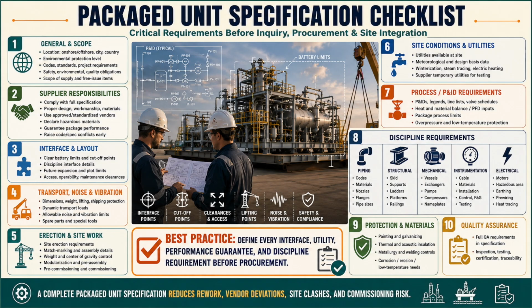The supplier must understand whether control is local, remote, or shared. They must know which logic resides in the package controller and which functions reside in the main plant system. A package that operates perfectly in isolation can fail during integration because permissives, trips, alarm priorities, fail-safe states, and communication ownership were never defined. Electrical requirements need the same clarity.